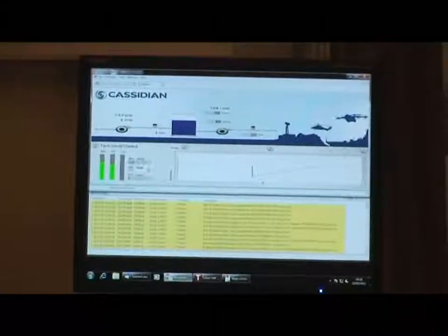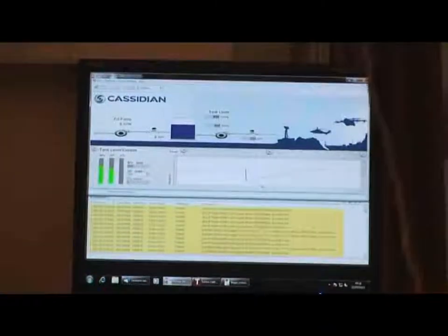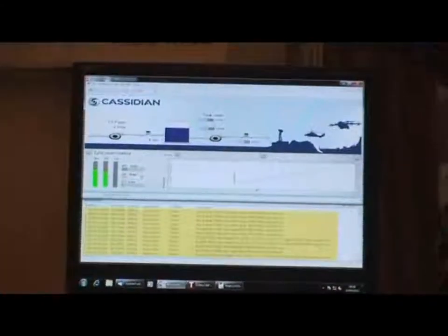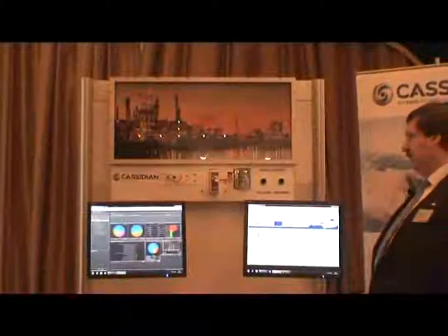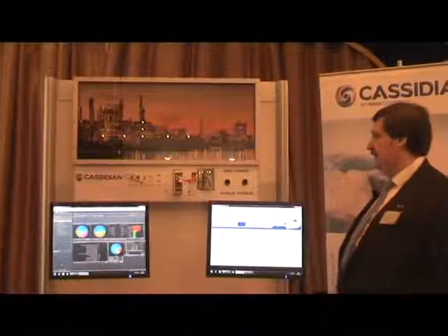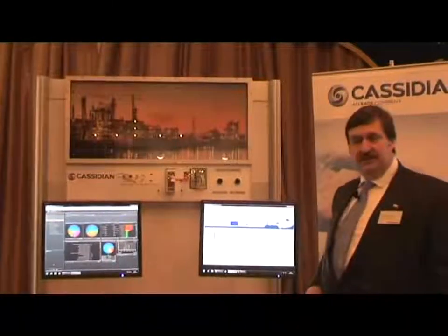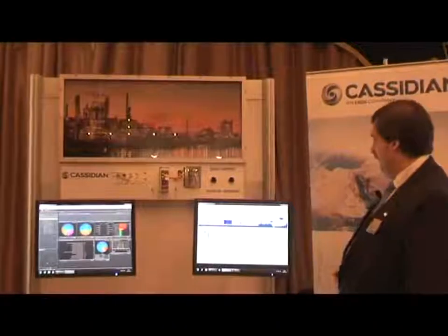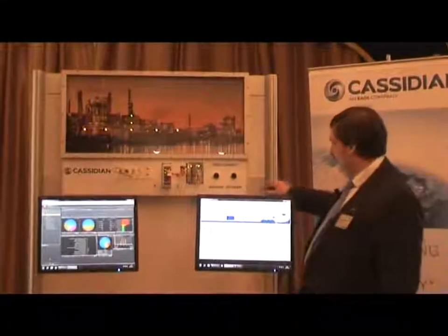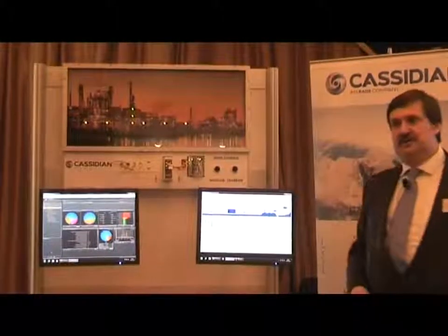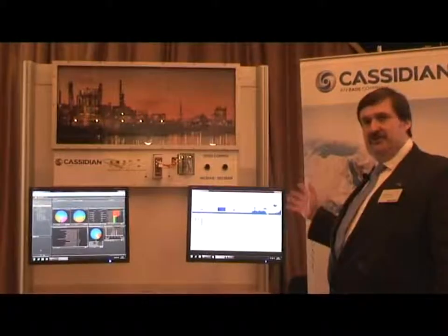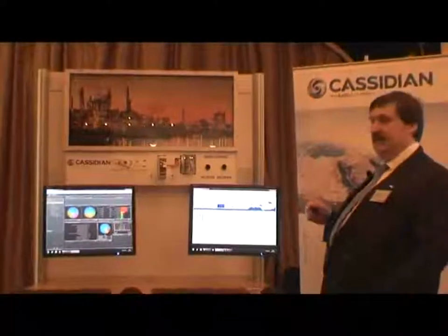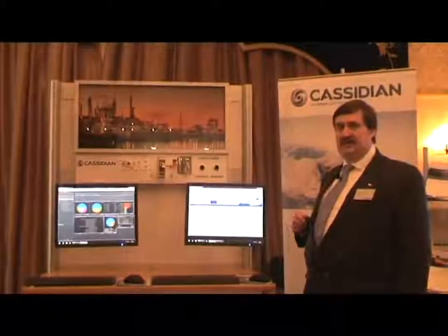What will happen, as far as you're concerned, is pretty much nothing, because the attack will be run, but up here we have standard pipeline operation, and over here as well. We're getting alerts on the screen telling us that illegal traffic is being blocked. So the Tofino device is actually detecting illegal packets and is stopping them. But if I want to change the pump speed, if I want to do the control, I can send the legitimate command, because the Tofino device recognises that as a standard command that we're allowed to send and will allow it to pass. So that is providing protection at the end of the system against attack.